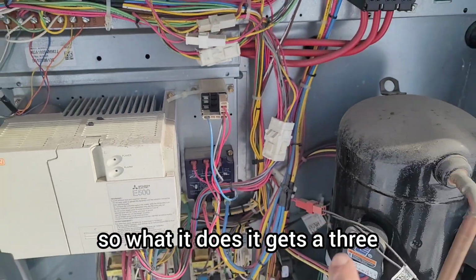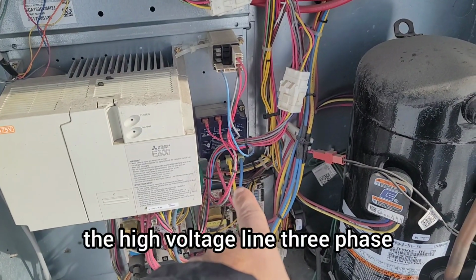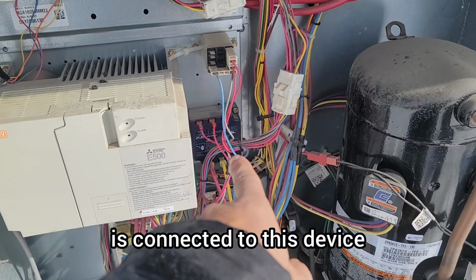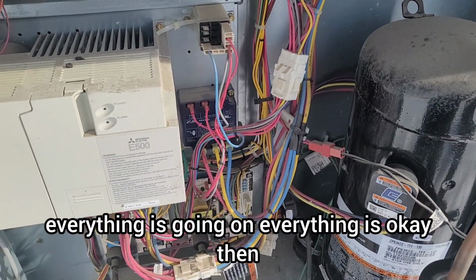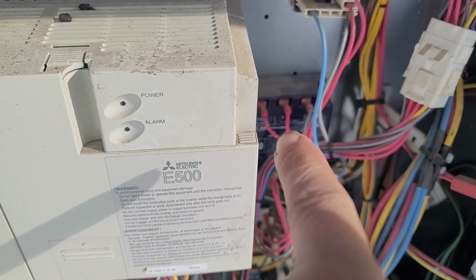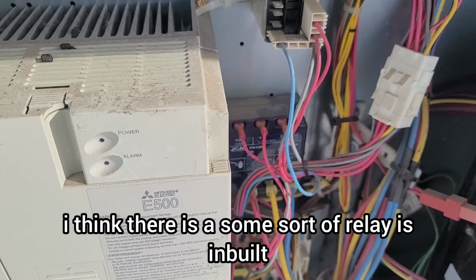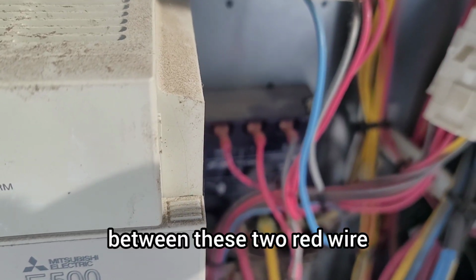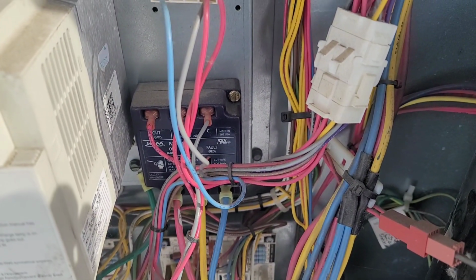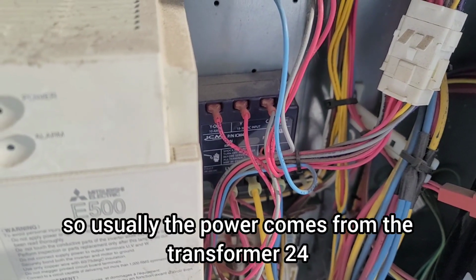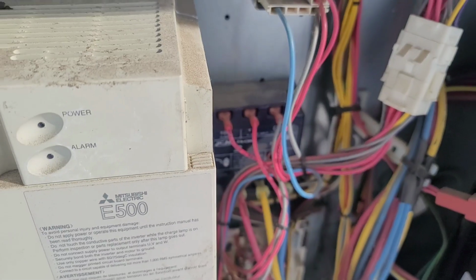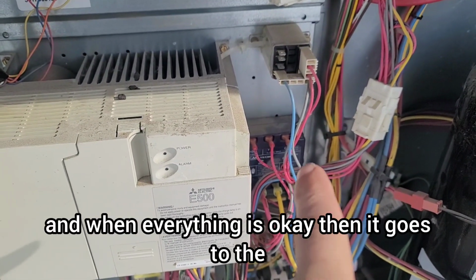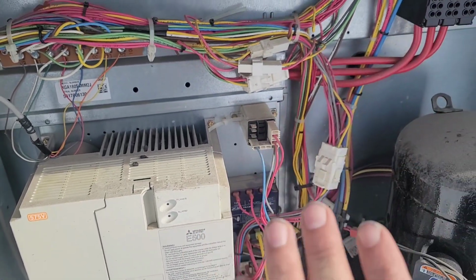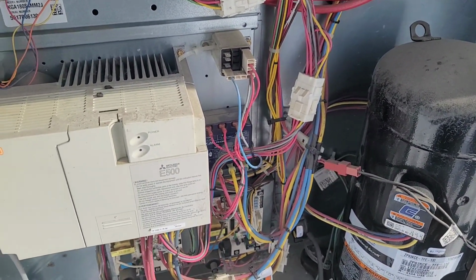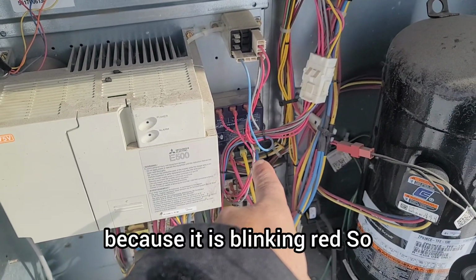So what it does, one of the high voltage lines of the three-phase is connected to this device, and whenever everything is okay, then on these two wires I think there is some sort of relay built in. When everything is okay, then there is continuity between these two red wires, and the third wire, the gray one, is common. So usually the power comes from the 24 volt transformer to this device, and when everything is okay, then it goes to the systems. So I think the switch between these two wires is open now because it is blinking red.